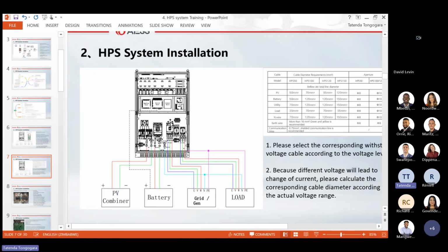So in the event that you have two HPS systems or three HPS systems, your battery cable length should be of the same length. Your grid cable, your AC input cable should be the same length from the point where you are connecting, and then your load to your combiner where you are combining your load, the length from the HPS should be of the same length.